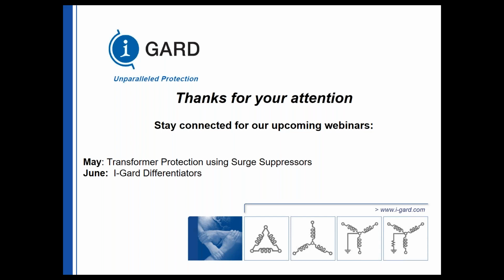Great. The next one is, how long do the green lights remain in the illuminated state? In order to save power on the capacitor, the green lights only stay on for about 5 seconds. So you press the test button, it undergoes the test, and the green LEDs, if they come on, establishing a safe work condition, will only stay on for 5 seconds. So once you've established electrical safe work condition, I guess the next step would be to apply your safety grounds or perform your work. But they don't stay on all the time, to help conserve the power that's stored in the capacitor.